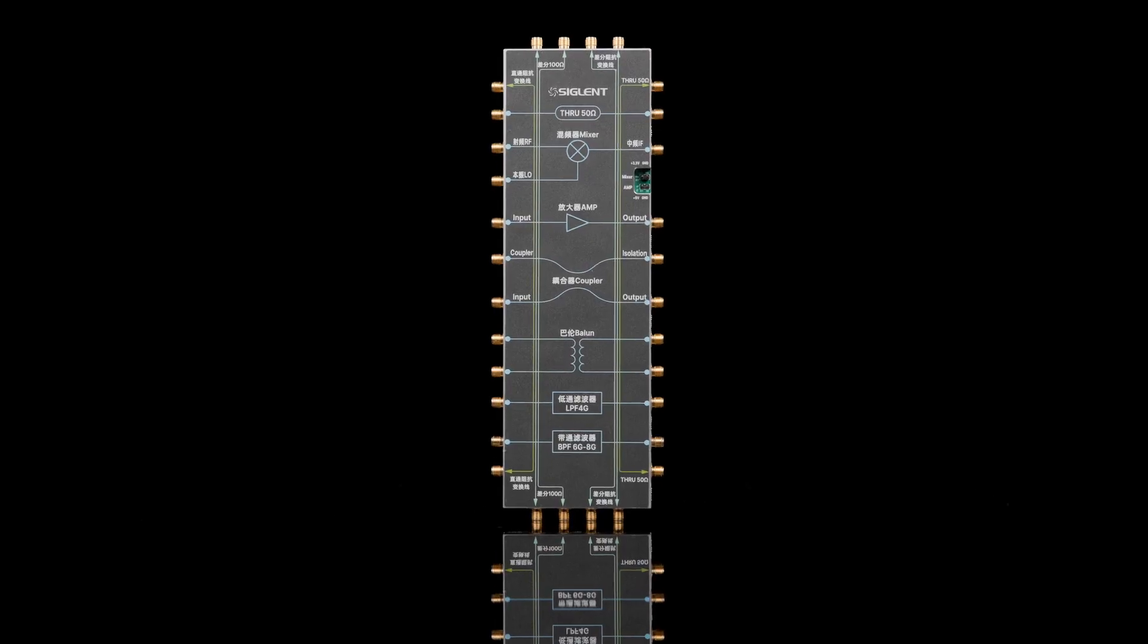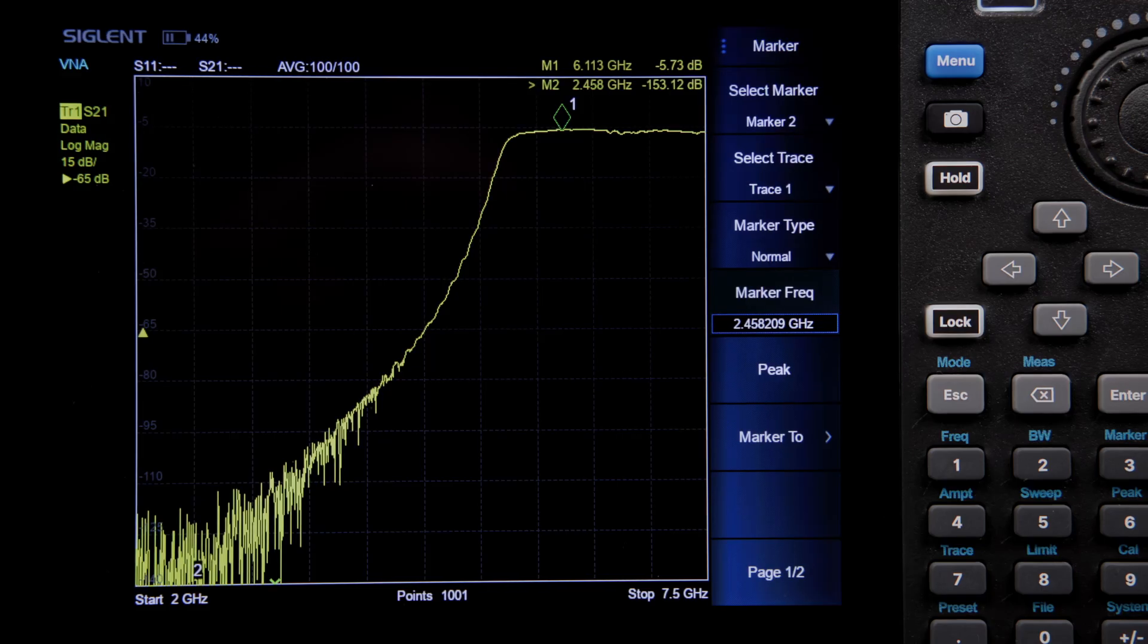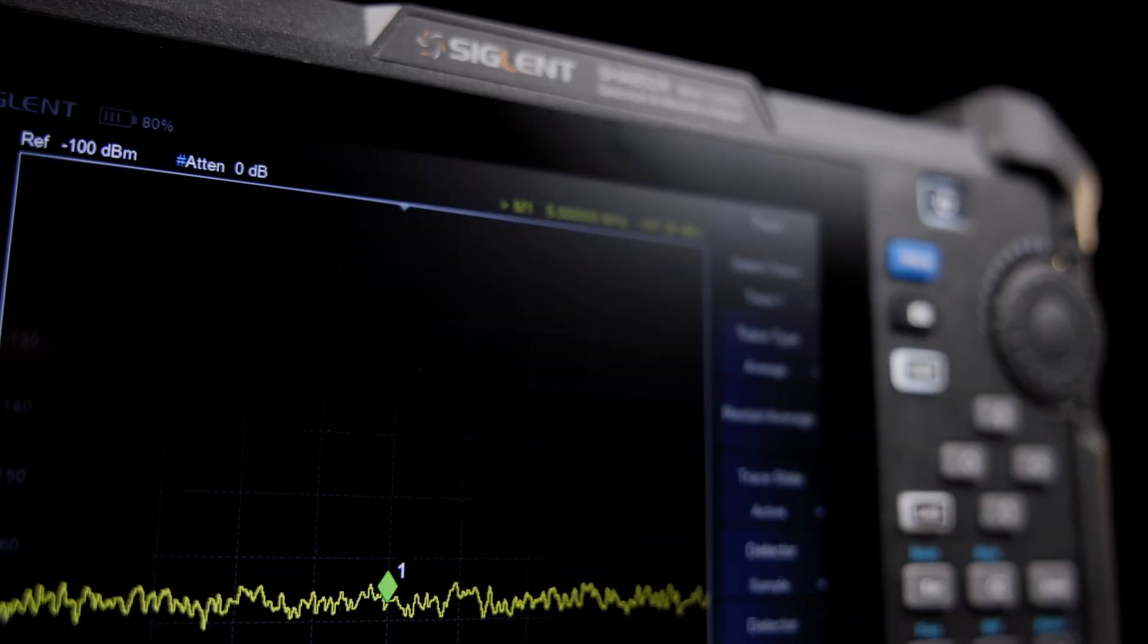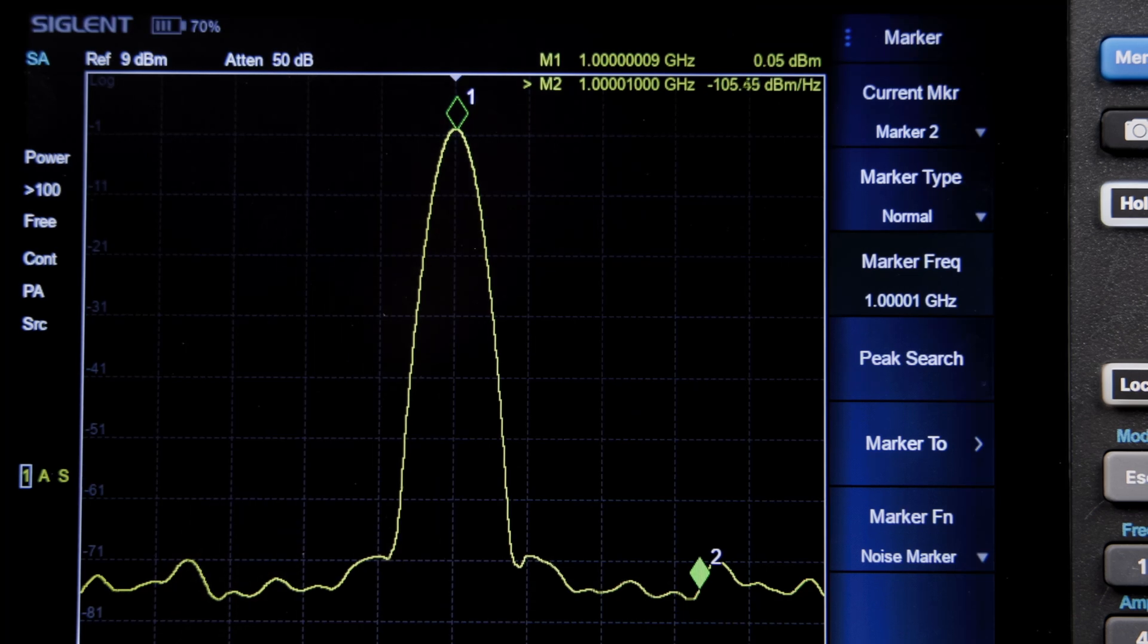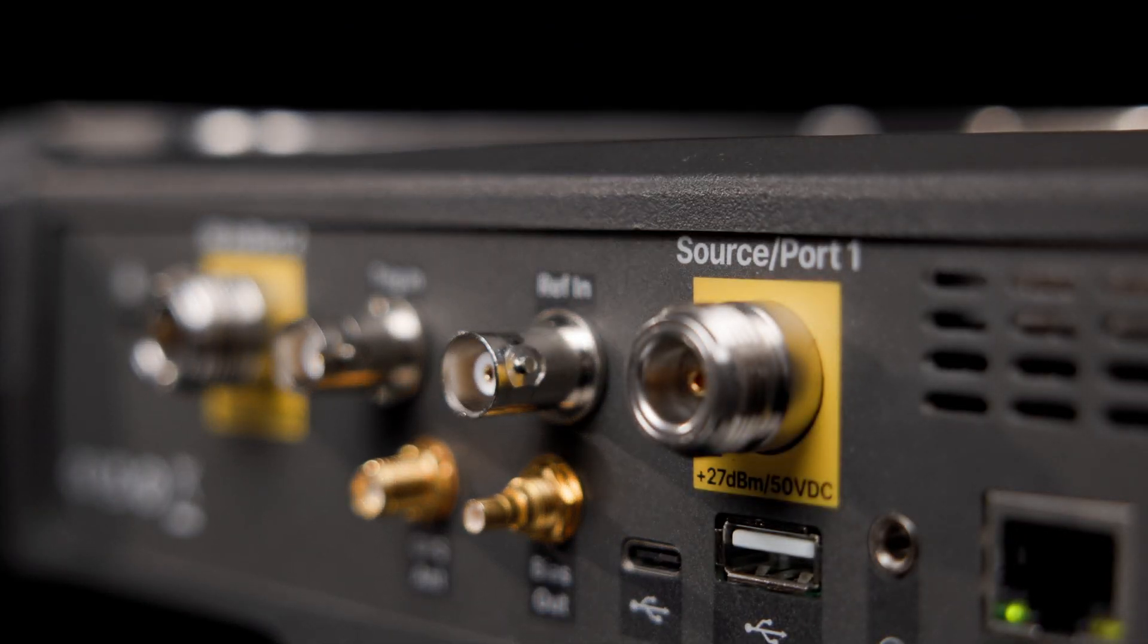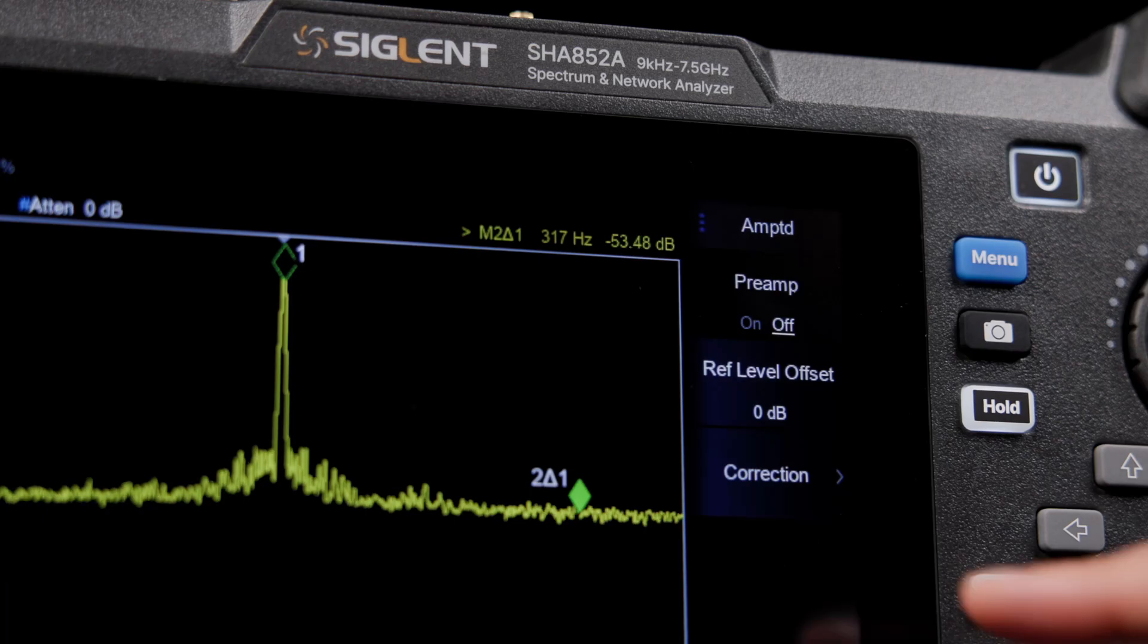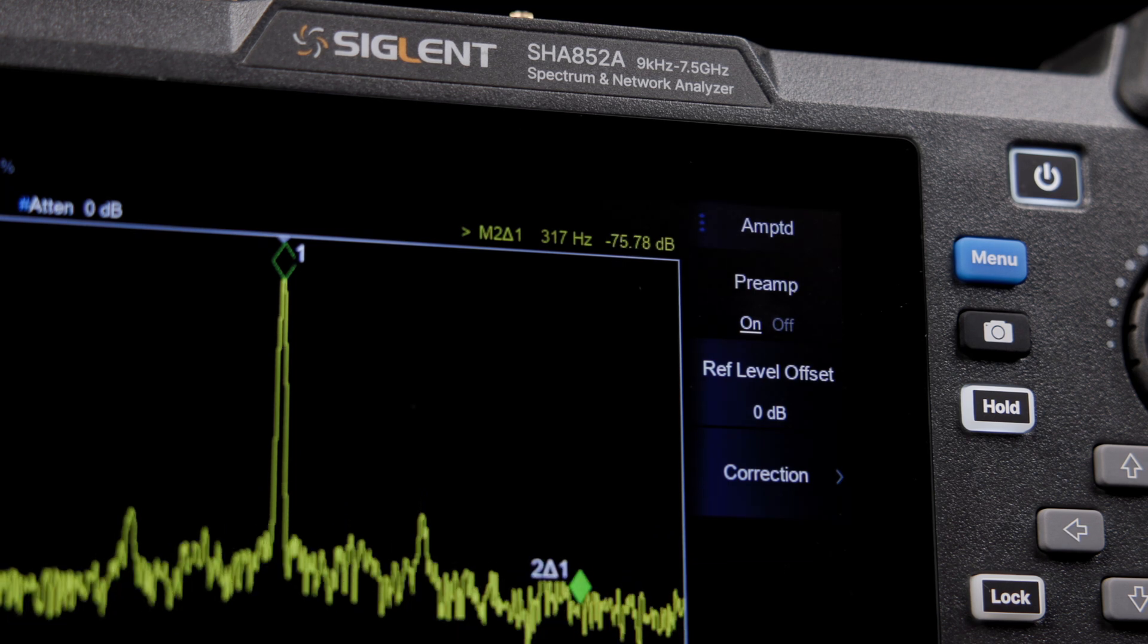Capture any signal with precision and confidence up to 7.5 GHz with a dynamic range of 114 dB, display average noise level as low as minus 165 dBm, and phase noise typically less than minus 104 dBc per hertz, an independent source up to 7.5 GHz and a 25 dB preamplifier are standard, making this analyzer well suited to capturing and analyzing sensitive signals.